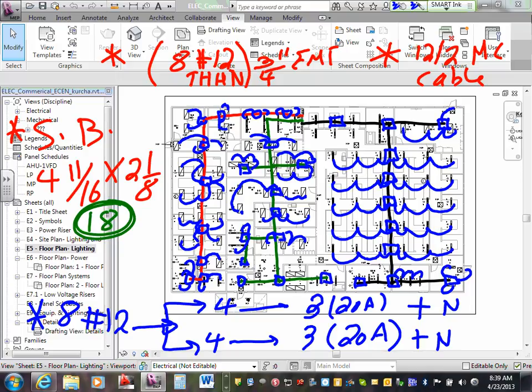If you fill this box, bring cable in every opening here, you will exceed the box fill for this. Cool? So if you guys bring no more than 4 to 6 in here, you're good to go, plus the conduits, of course, coming in. Okay, here's my boxes. I loop them in. I went to this room, guys.